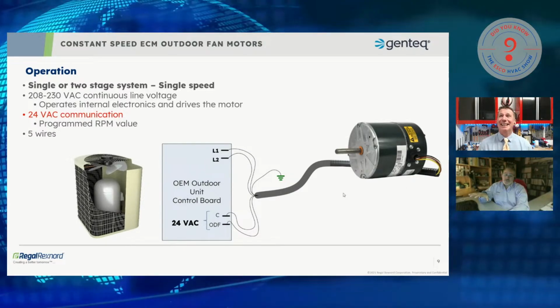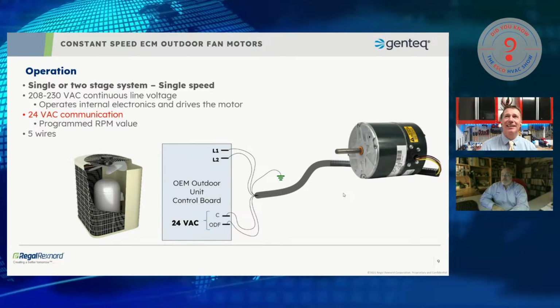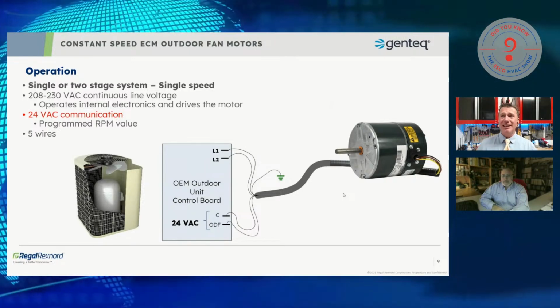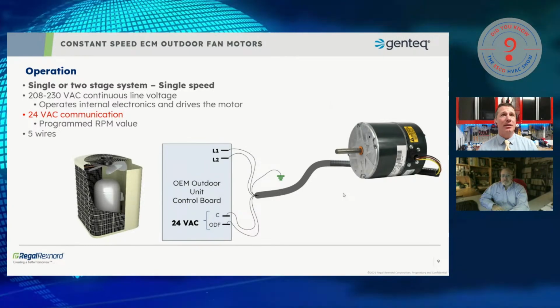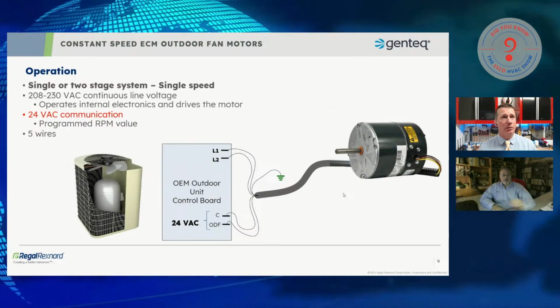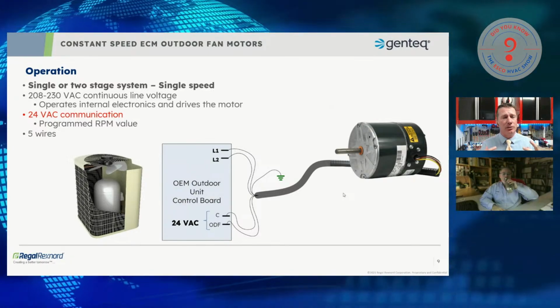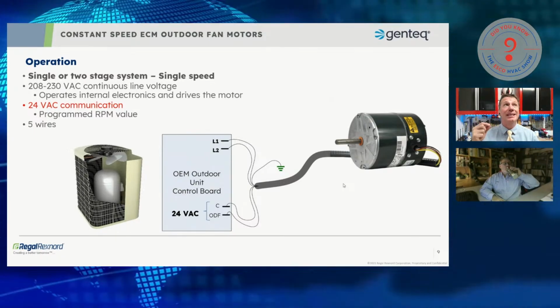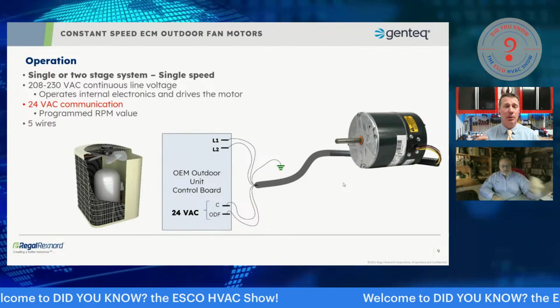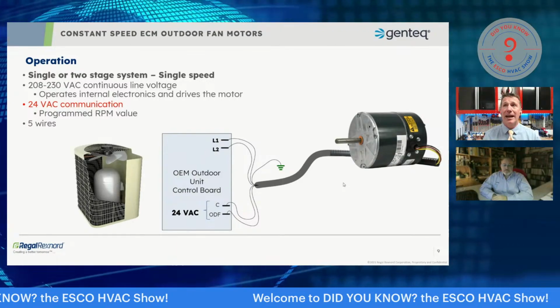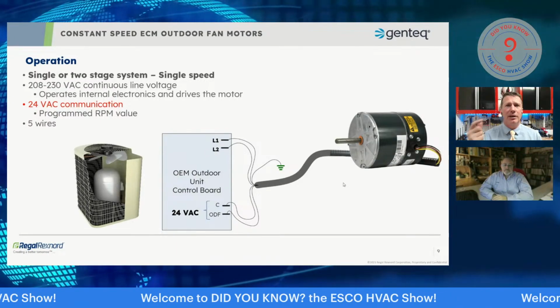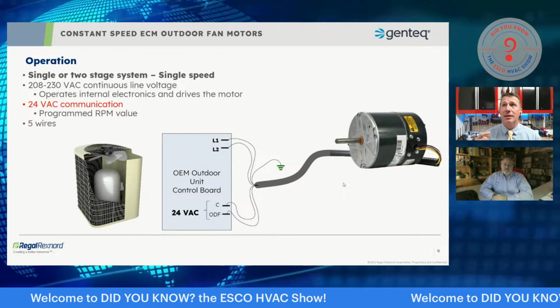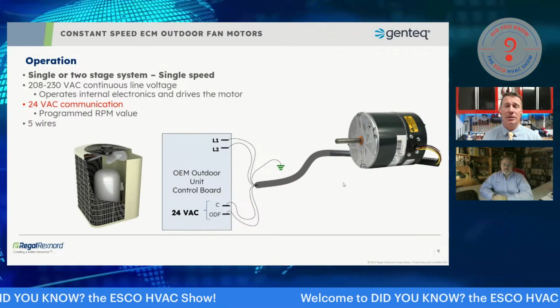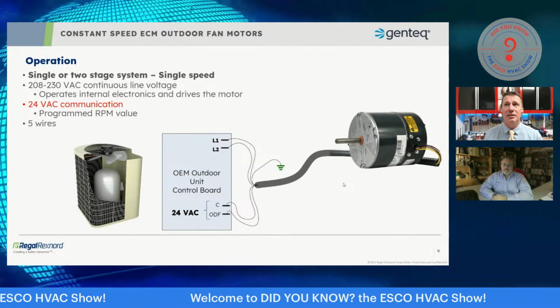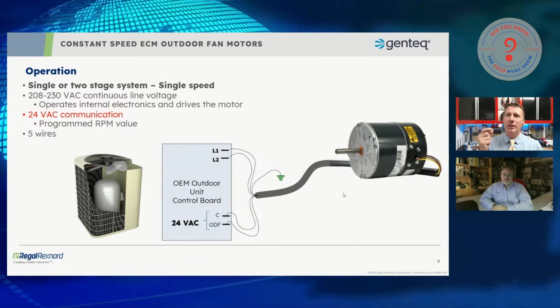So any questions on the 24 volts before we move on to the dreaded PWM? No, that's pretty good. I think this is a good time to see if anyone in the audience does have questions, because we really are talking quite a transition going from PSC into ECM, and then we're going to be getting into the PWM, pulse width modulation, which we've seen in our variable, especially our constant airflow that's using a variable PWM, just to set the up or down stagings of our motor, but not in our condenser.